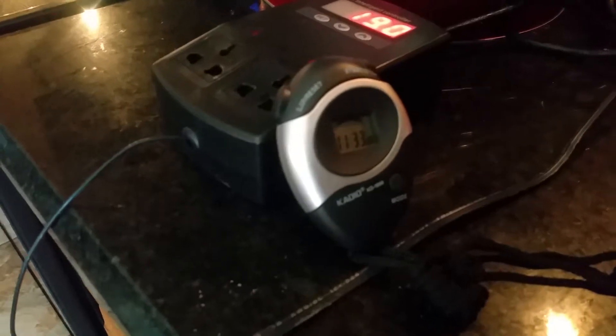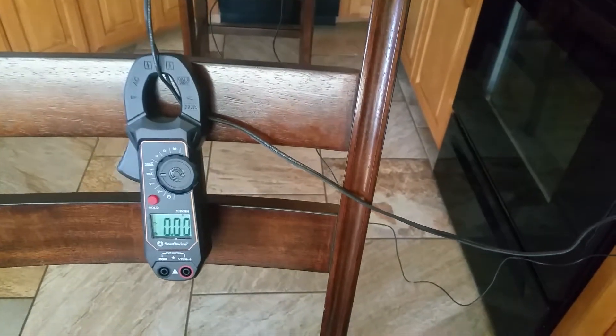It's still not on at 11.5 minutes, still sitting at 19 degrees Celsius. At the 13-minute mark the manufacturer says these units are not supposed to be cycling on and off. Then at 13 minutes and 20 seconds it came back on — so it was off for just over four minutes. We're still at 19 degrees Celsius.